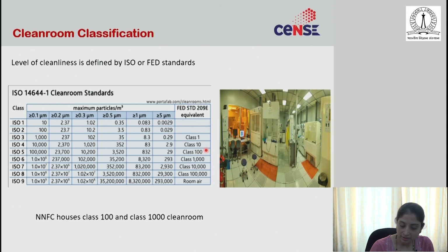From class 1000 to class 100, you can see the change in magnitude in the number of particles. For example, for 5 micron particles, class 1000 can withstand around 293, while in class 100 it is 29. But for smaller particles, the number increases. One thing to remember: the smaller the particle, the greater the adhesive force, and the more difficult it is to remove from the substrate surface. So as I told you, NNFC houses both class 100 and class 1000 clean rooms.